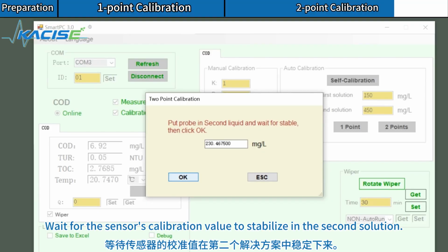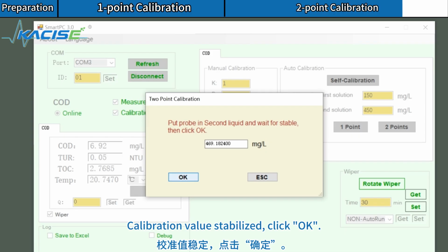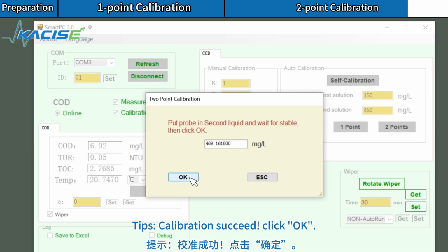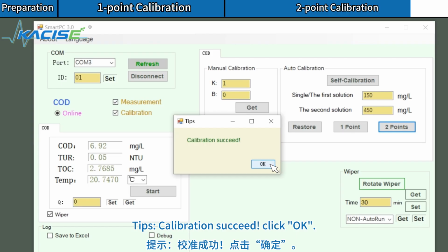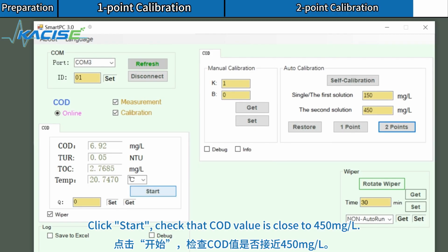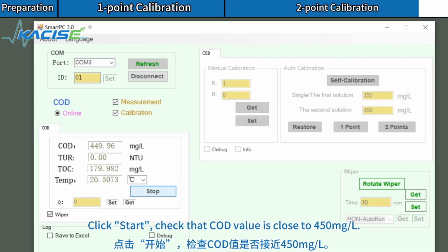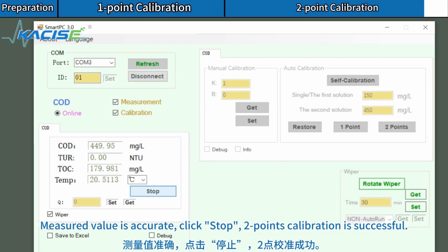Wait for the sensor's calibration value to stabilize in the second solution. Calibration value stabilized. Click OK. Tips: calibration succeed. Click OK. Click Start. Check that COD value is close to 450 milligrams L. Measured value is accurate.